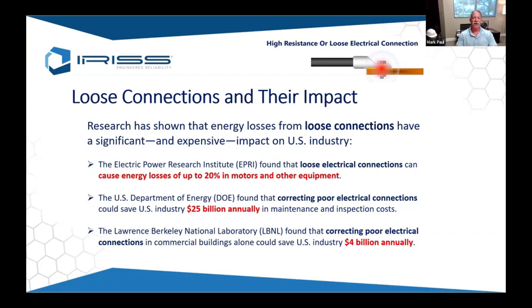To the eye, visibly, you can't see it. To the ear, you most likely won't hear it, even if there's some slight arcing going on, not until it gets pretty extreme. But in this loose connection, not only is heat being created, a lot of energy is being lost. Loose connections in motors can cause up to a 20% energy loss. $25 billion annually is being lost to poor electrical connections in US industry today, and in commercial buildings alone, $4 billion annually is being lost.